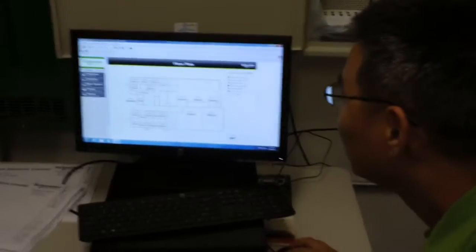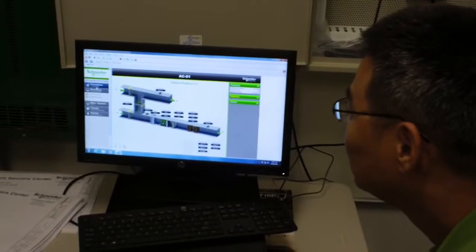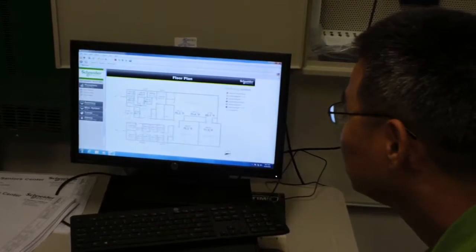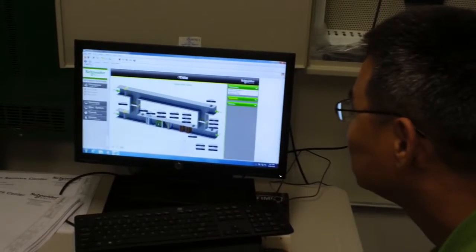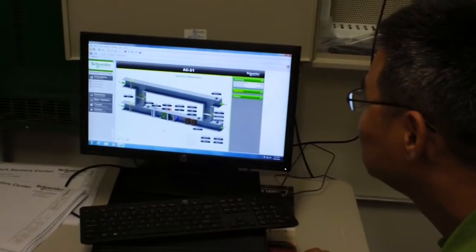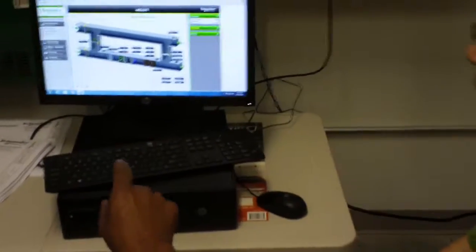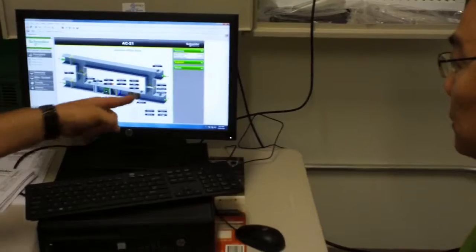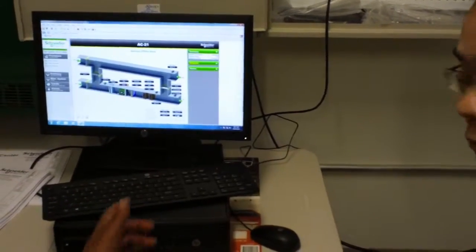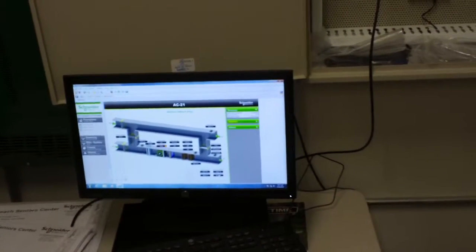So there'll be a bypass, and then you guys have a temperature control in the supply air. See that bypass? There it is, right there. At 0%, so everybody's 100% open, or pretty close to 100% open. Yeah, then the pressure is nothing right now, and you need to have static air pressure, so you don't have to worry about your unit short cycling and freezing itself up.